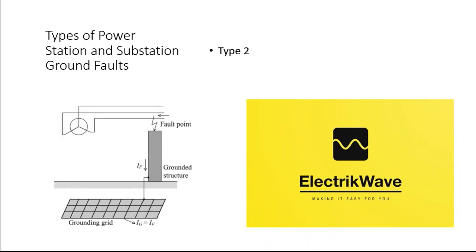Let's see Type 2 fault. Fault within local substation, the neutral is only grounded remotely, and all the fault current flows from the fault point through the substation grounding grid into the earth.